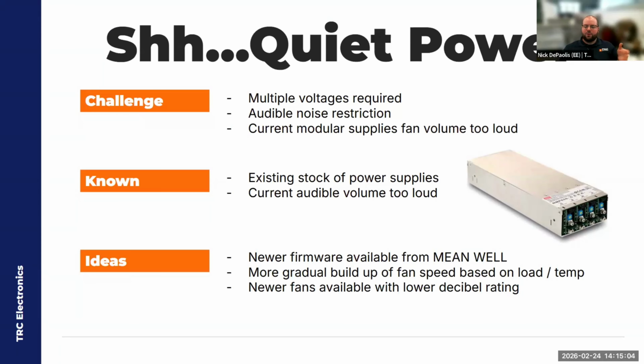Now, even though we're swapping out that fan, which is listed under the CB report as a critical component, Mean Well had it already certified, just listed as an alternate, so we didn't have to go through a whole lengthy and expensive recertification process.